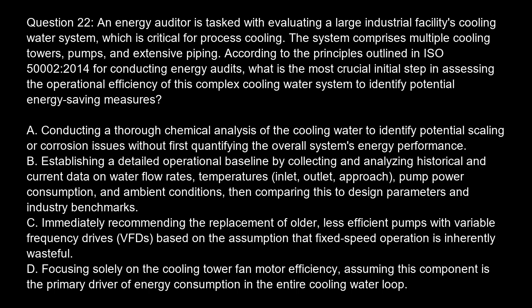The correct answer is B. Establishing a detailed operational baseline by collecting and analyzing historical and current data on water flow rates, temperatures, inlet, outlet, approach, pump power consumption, and ambient conditions, then comparing this to design parameters and industry benchmarks. Explanation. The question probes the understanding of how to systematically evaluate and improve the efficiency of a cooling water system as part of an energy audit, aligning with ISO 50002, 2014 principles.